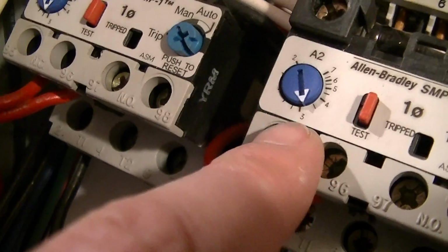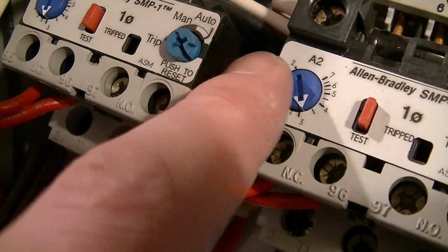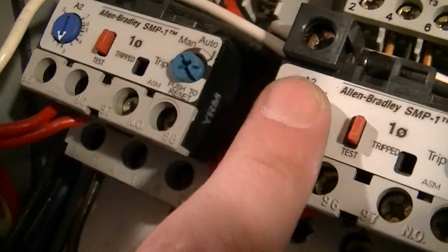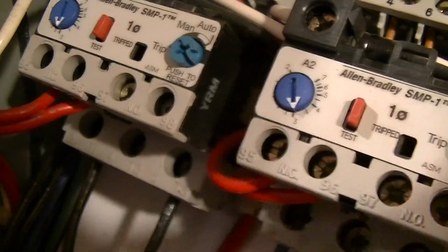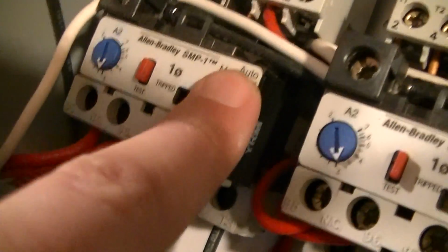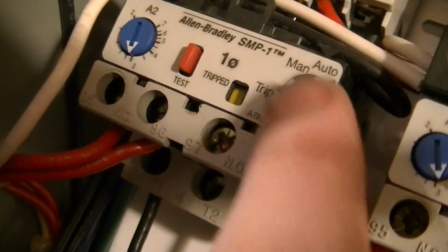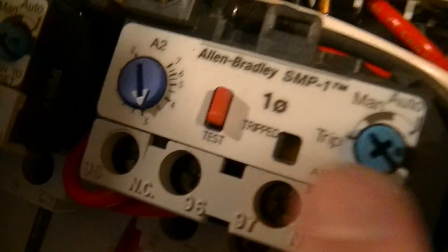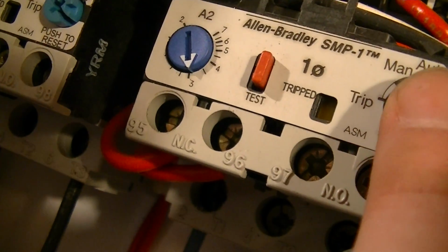So the way these work is you just have a little dial that you set to the current, in this case 3 amperes, but it's settable anywhere from 2 amperes to 7 amperes, and when it exceeds 3 amperes for an extended period of time, it trips, which you can manually do by just pushing down and turning the little blue thing on the right, and just to reset it, there's a little yellow flag window just to say that the thing has tripped.